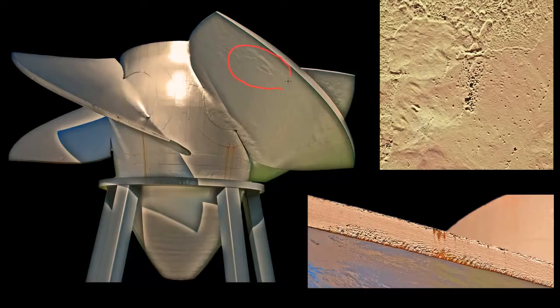On the low-pressure side of the turbine blade in approximately this location, we can see some evidence of the type of surface pitting that is typical of cavitation damage.